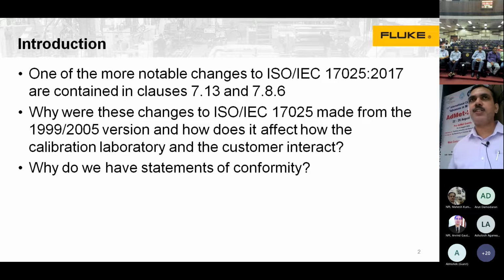In clause 7.1.3, it says that when the customer requests a statement of conformity to a specification or standard for the test or calibration, like pass, fail, in tolerance or out of tolerance, the specification or standard and the decision rule shall be clearly defined. Unless inherent in the requested specification or standard, the decision rule selected shall be communicated and agreed with the customer. And 7.8.6 is about the statement of conformity or the decision rule. The decision rule describes how measurement uncertainty will be accounted for when stating conformity with a specified requirement.